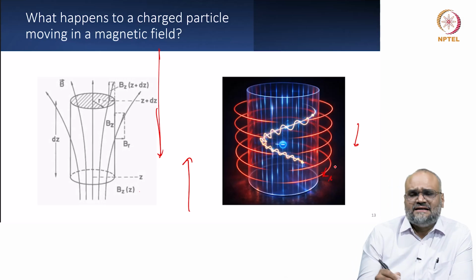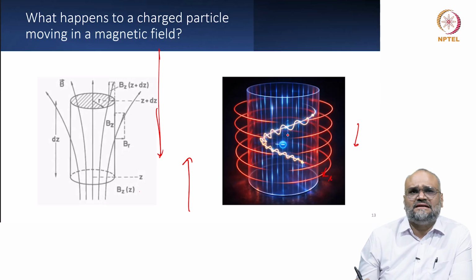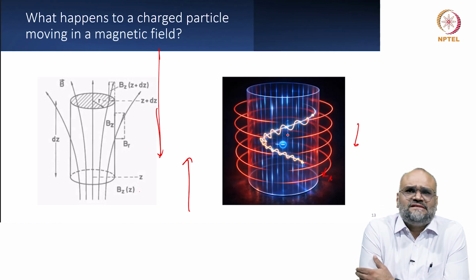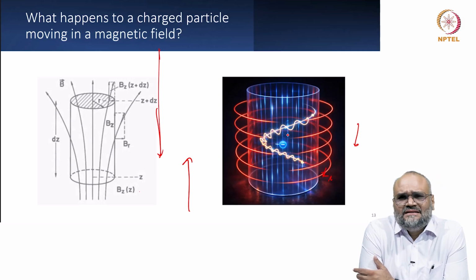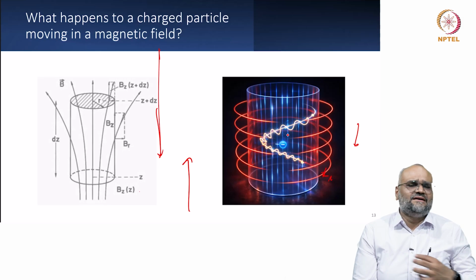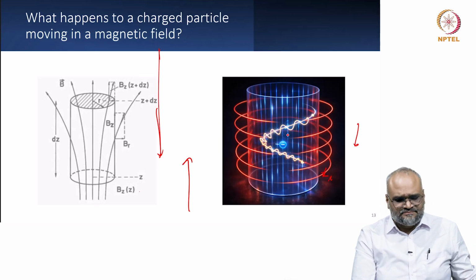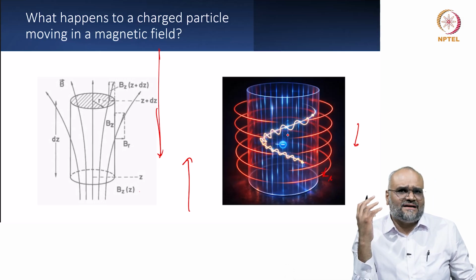When a charged particle, that is an electron, enters this kind of a field, it experiences the Lorentz force and it follows a helical path. In some of the older microscopes, you would see the effects of this helical path influencing the image that you record, and you had image rotation. The newer microscopes, because the electron beam trajectory is reasonably well understood, compensate for this image rotation, and your image remains stable with various magnifications. So this is how an electron beam moves in an electromagnetic lens.